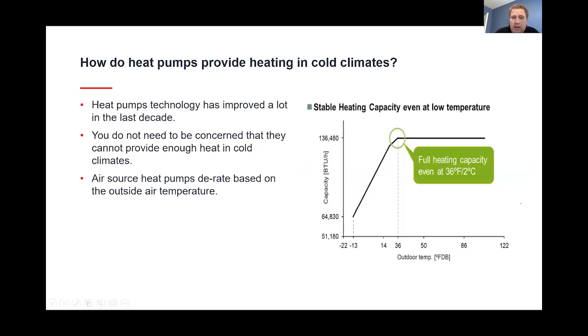Now the second chart here is for a domestic hot water heater, which has harder derates than VRF, but still operates all the way down to negative 35. We just don't have data down there. And you really don't need to be too concerned with the derates as long as you work with your manufacturer to properly size the project for the correct ambient temperatures to ensure you always have your hot water.